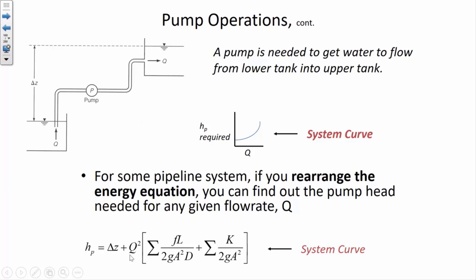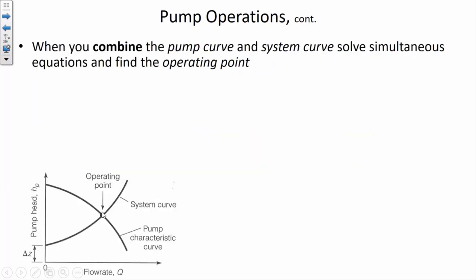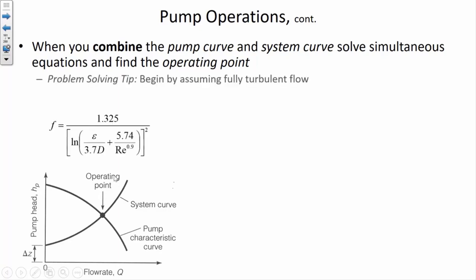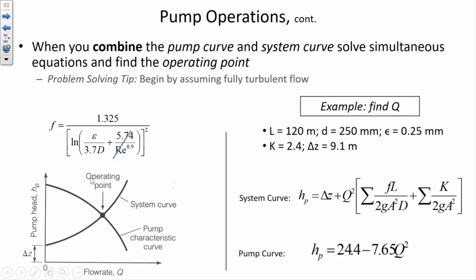In this illustration, water is being lifted from a lower reservoir and is being pumped up to this upper reservoir. Along the way we're overcoming friction losses, there's a couple of pipe bends so there would be local losses. There's a delta Z. When we have a picture of the system or a description, we could come up with a system curve. This is different from the pump curve. The characteristic of a typical shape of a pump curve is that there's an intercept and then it's sloping downward. That's the pump performance curve. The system curve has an intercept as well, but then the curve is going up. Because what this represents is the amount of pump head that's required to achieve a certain flow rate. The curve is getting higher and higher at an increasing rate because we know that the head losses are increasing as the flow rate goes up by squared power.